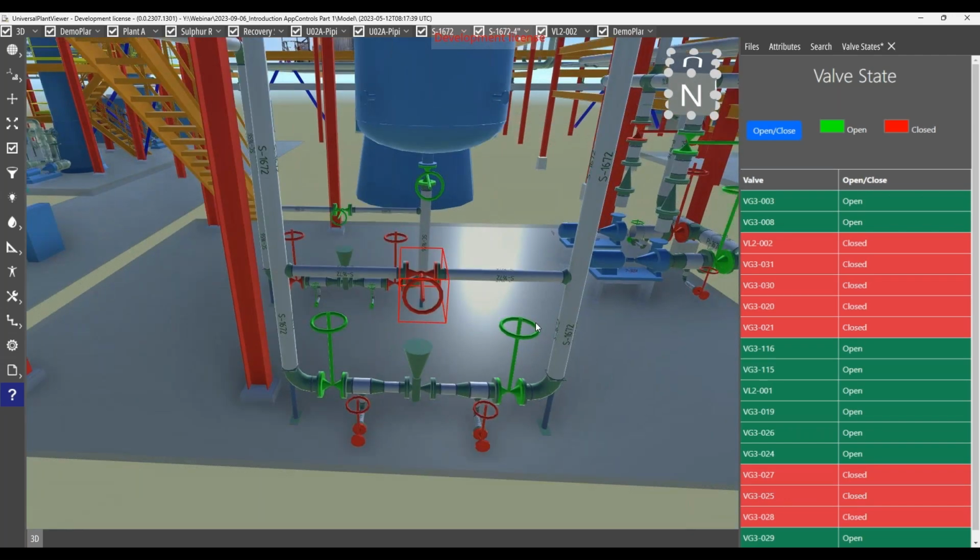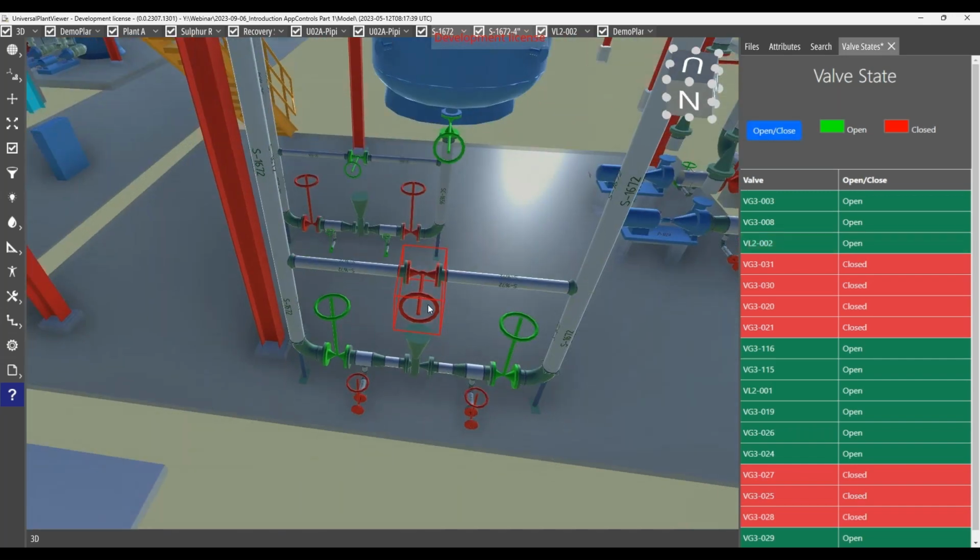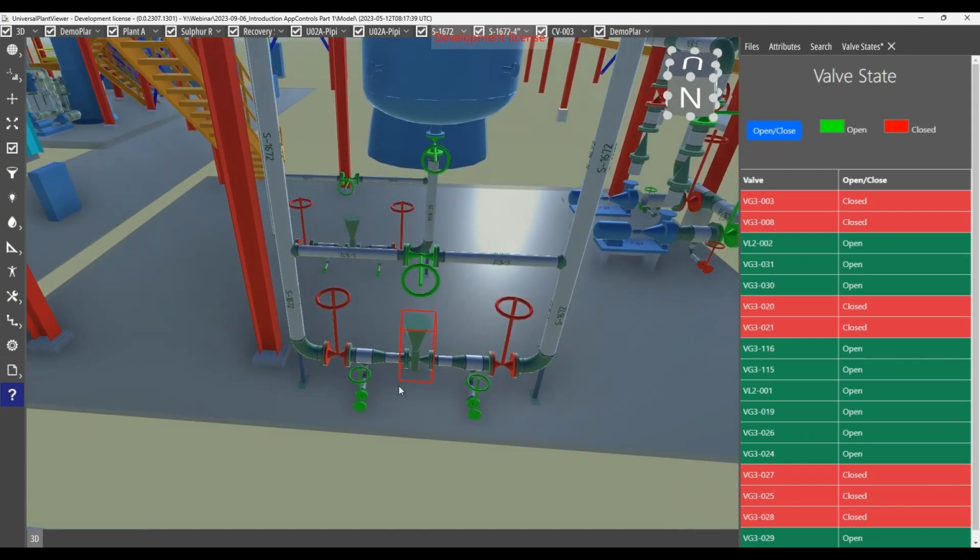So now I can say, for example, I need to open up this bypass valve. I need to close these two valves and open up these drain valves. And now I would be able to remove this valve down here. And this could be all recorded and either then directly performed via automatic valves, or for example, printed onto a log list and handed to an engineer on site that then performs these actions.